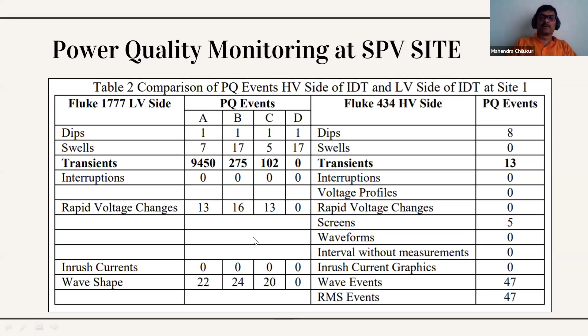In fact, this particular table shows two power quality meters. One is a Fluke 434, and one is another model. One is on the LV side and one on the HV side. We are trying to show the events seen on the HV side and on the LV side. On the LV side of the inverter you will see so many, and on the HV side only very few. So you have to understand that if you monitor power quality only at the PCC, you are measuring only harmonics there, nothing else.